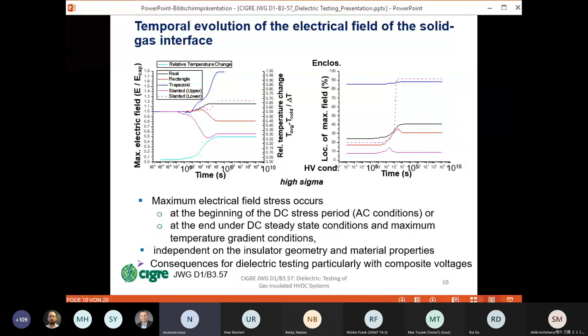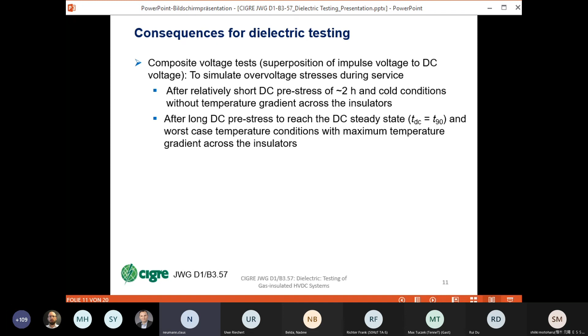That means after a relatively short DC pre-stress of about 2 hours and cold conditions, without any temperature gradient across the insulator, that could be a critical case, but also after long DC pre-stress to reach the DC steady state, and the worst case temperature conditions with the maximum temperature gradient across the insulators. And that means additional testing during the transition time is not necessary.